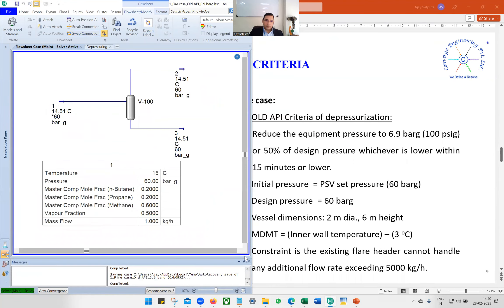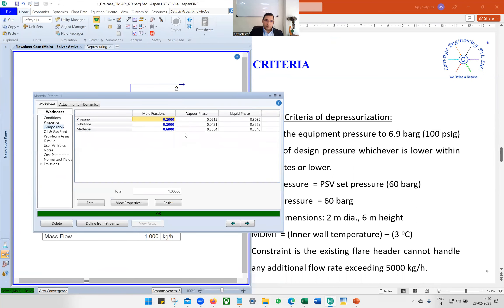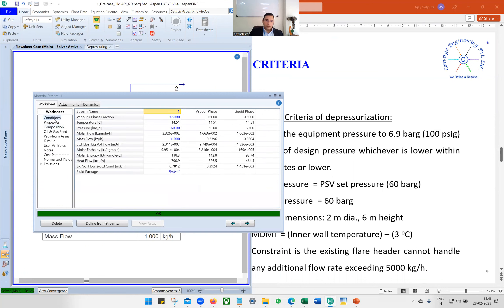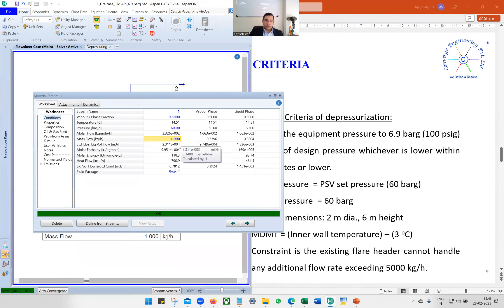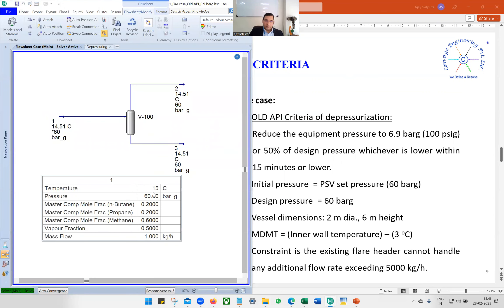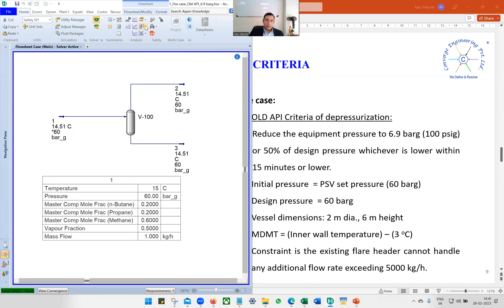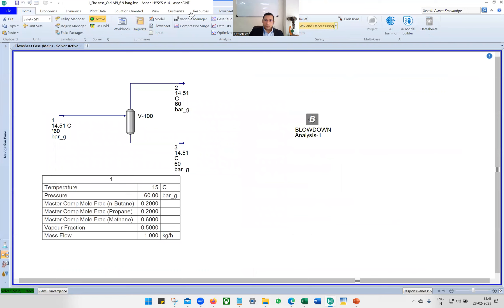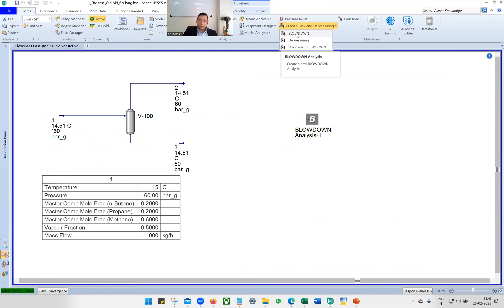For stream number one, the composition is propane N-butane 0.2 each and methane 0.6. The pressure is 60 bar gauge — which is the design pressure of the equipment — and the vapor fraction is 0.5. It will calculate T-sat as approximately 14.5°C. Then we go to Home, then to the blowdown and depressuring dropdown box, and select blowdown.